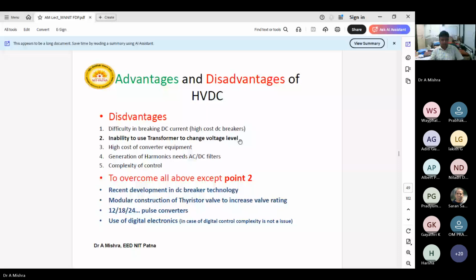The third disadvantage of DC transmission will be the high cost of the converter equipment. Definitely, if you are using the rectifier station, converter station, then if it is a 6 pulse converter, you have 6 firing circuits, that much control circuit. So all that will increase the cost of the converter. Generation of harmonics needs AC and DC filters. This is the thing that I told at the time of the disadvantages of the rectifier, in the introduction of power electronics, that if you are using any semiconductor based devices, you will introduce harmonics. But for those harmonics, a filter will be required.